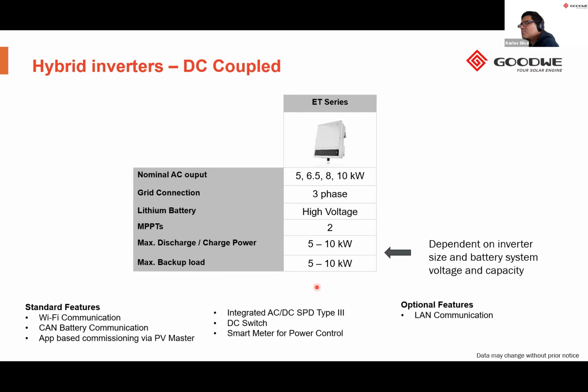And one of the main advantages, or one of the unique selling points of our inverter, is that it does have a backup output, and depending on the power class of the inverter, the backup loads can be from 5 to 10 kilowatts. In terms of the standard features that we offer with the ET series inverter, we offer Wi-Fi communication. There is the CAN bus battery communication. All the commissioning is done via the PV Master app, which I will go through in a moment. We do have integrated AC/DC SPDs type 3. However, if you need type 2 or type 1 SPDs, then I would recommend you use external SPD components, such as from DEHN or Phoenix Contact.